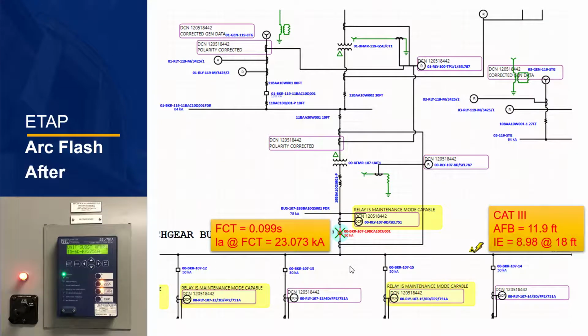With maintenance mode switches, you get the best of both worlds: reliable operation during normal conditions and safe conditions during maintenance activities. Maintenance mode switches enable or lower the pickup of the instantaneous overcurrent function of the protective relays, usually at the expense of coordination between devices.